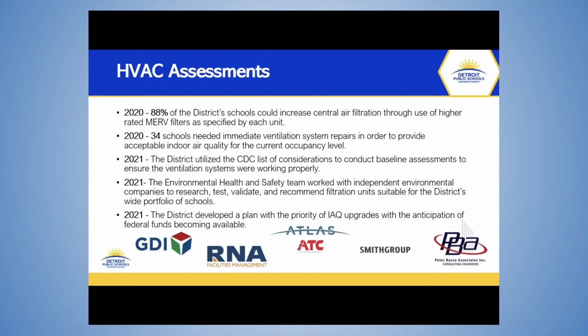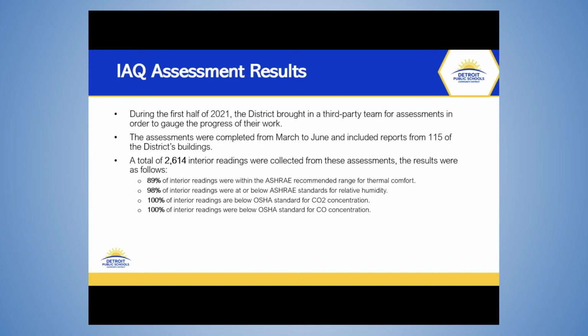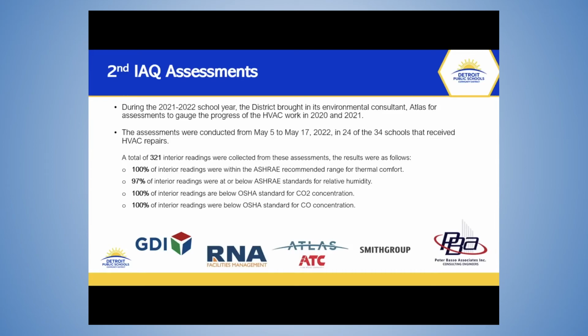Our indoor air quality assessment results showed 89% of our interior readings were within ASHRAE recommendations for thermal, that's temperature, 98% were below ASHRAE standards for relative humidity, 100% of our buildings were below OSHA standards for CO2, and 100% were below OSHA standards for CO, carbon monoxide. With that being said, we conducted a second indoor air quality assessment and an assessment of our HVAC equipment on those 34 buildings that needed immediate repairs in our previous assessment in 2021.